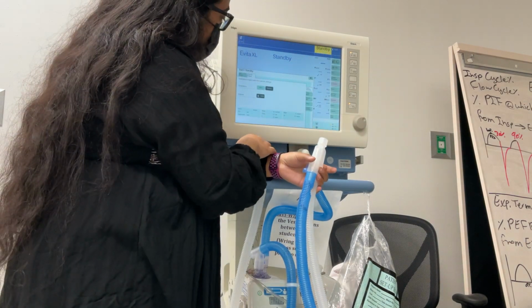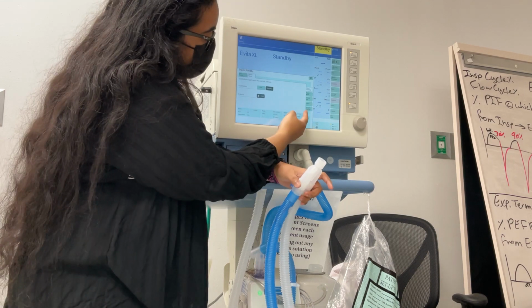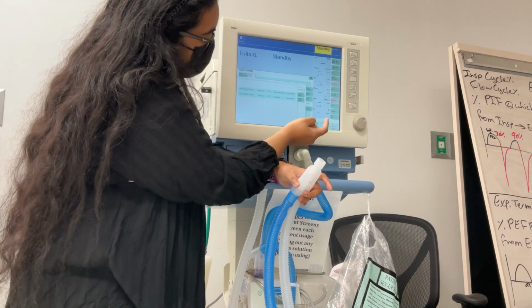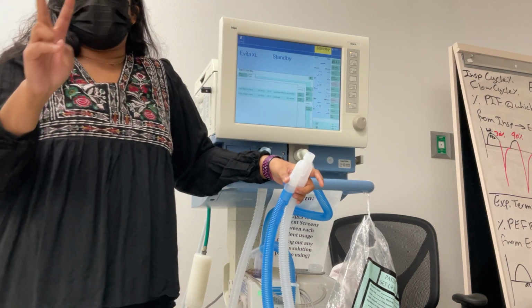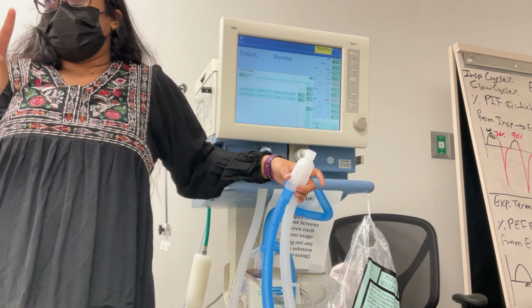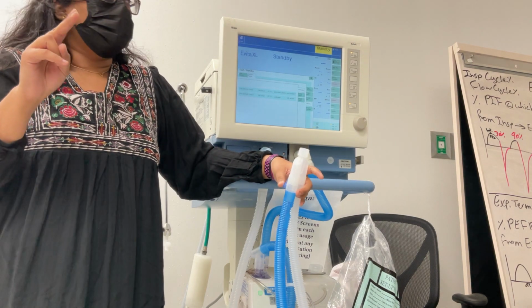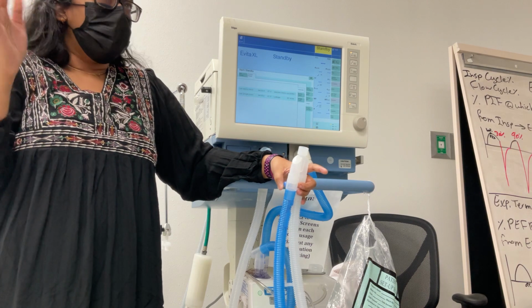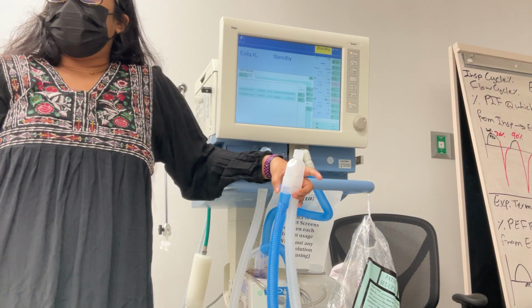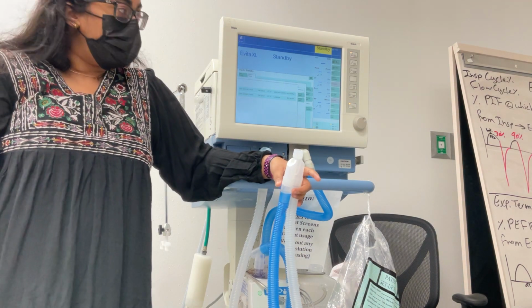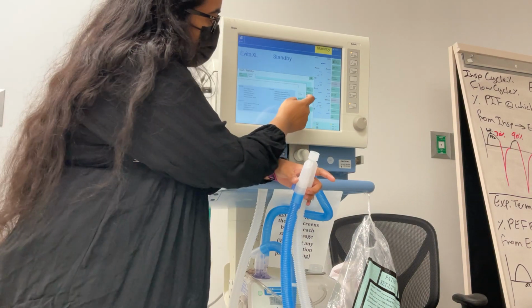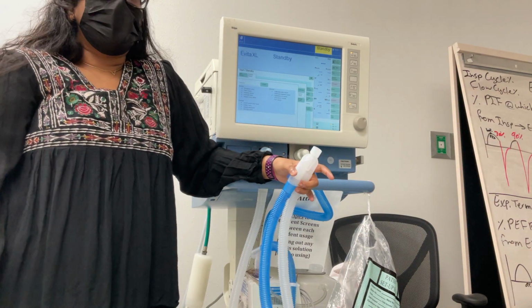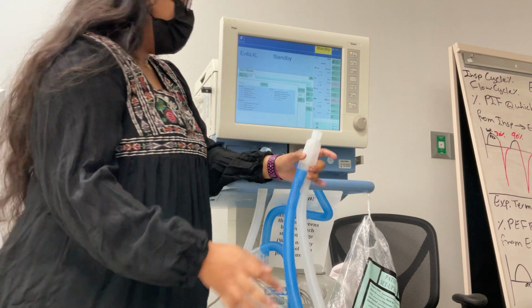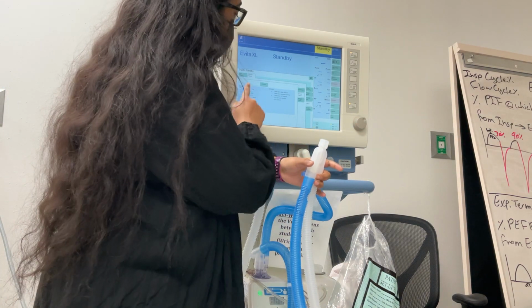Okay. So to start off, on this side over here, you're gonna hit check, and then you've got 2 checks to do on both Draegers. You're gonna do device check and breathing circuit check. Breathing circuit check is gonna look for leaks. You want at least under 300 mils for the leak for it to be passing and acceptable to use on a patient. I usually start with device check because it takes longer. It's about 8 minutes. So find something to talk about during your check off, I guess.